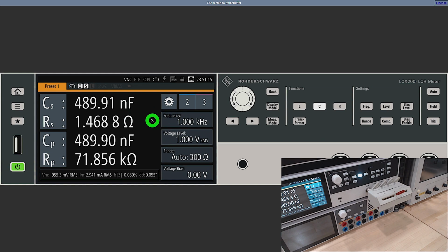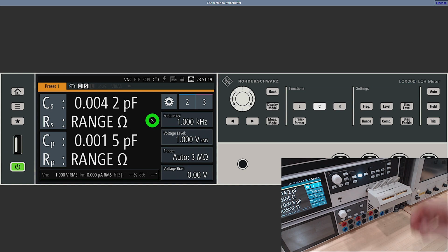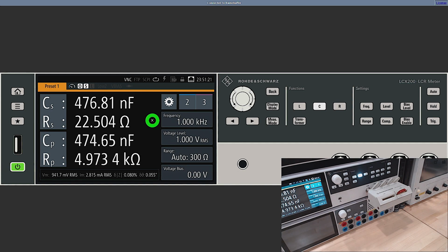Now I can go ahead and change that capacitor and put in the one that I've modified. It should behave quite a bit worse than the original one. And let's see, look at that. We're looking at 22.5 ohm now of RS and about 5 kilo ohm for RP. This is a lot worse capacitor. Normally a capacitor like this would be essentially rejected. Now you may ask, well, what if I want to know what the leakage of this capacitor is? That leakage is that parallel resistor that I purposely added to the capacitor. That's going to have to be done at DC. You cannot measure this using this equivalent circuit model at these frequencies.